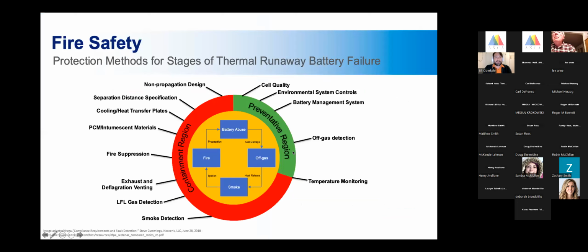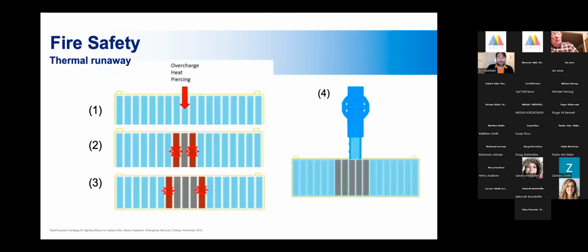These are all of the different measures. We've got our prevention here: start with good cell quality, a good battery management system that can isolate cells and cool them down if needed, and off-gas detection. Once we've entered thermal runaway, there are a number of things we can do to contain it, listed here: good fire suppression, cooling and heat transfer plates, and a non-propagation design in the system. These are all the things we can do to address the somewhat rare instance of an energy storage system catching fire or going into thermal runaway.